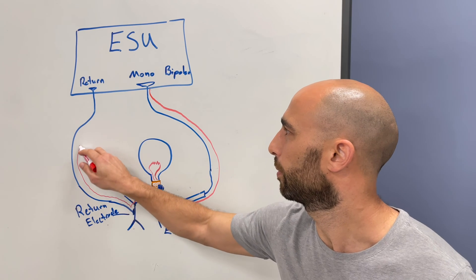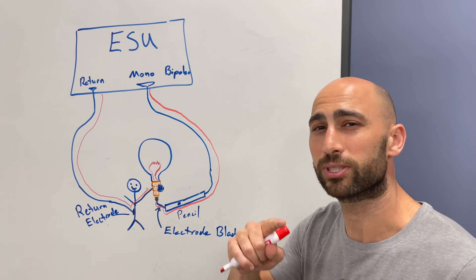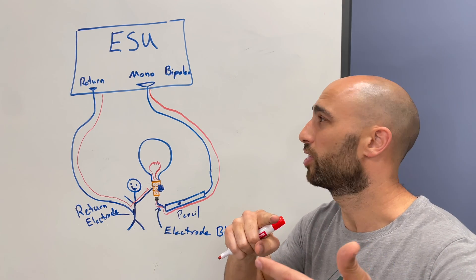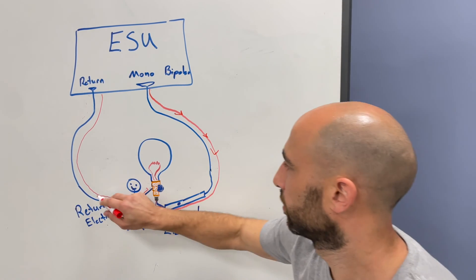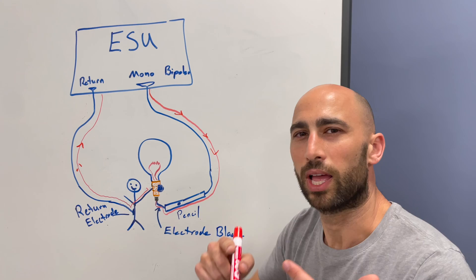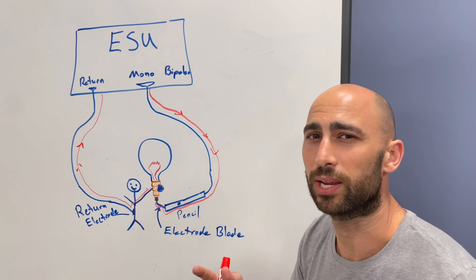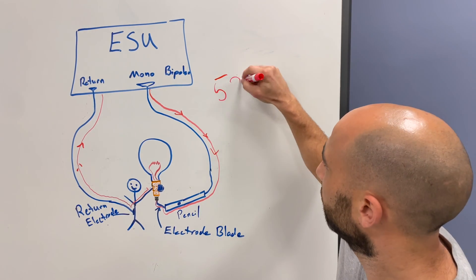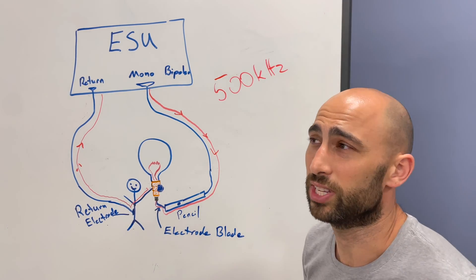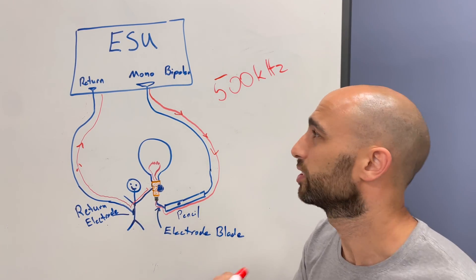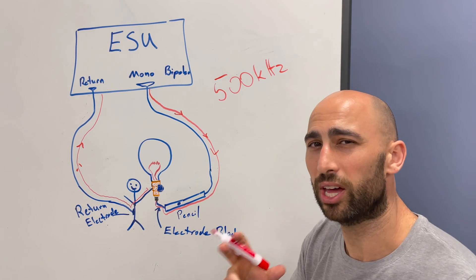Then it goes back into the return port of the ESU, completing the circuit. Because this is AC, the direction of current is going to flip — current goes this direction, then at some point it flips and goes in the opposite direction, but the path stays the same. Most ESUs will have a frequency of around 500 kilohertz, so it's switching extremely fast. Really, both the electrode and the return electrode can be thought of as active.